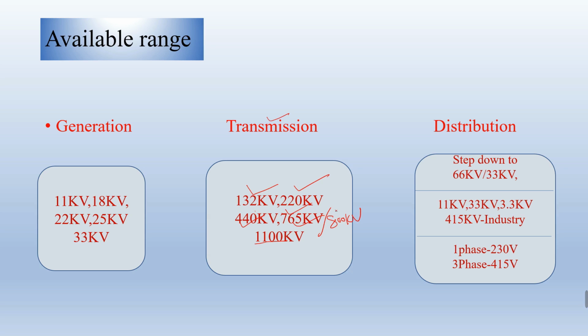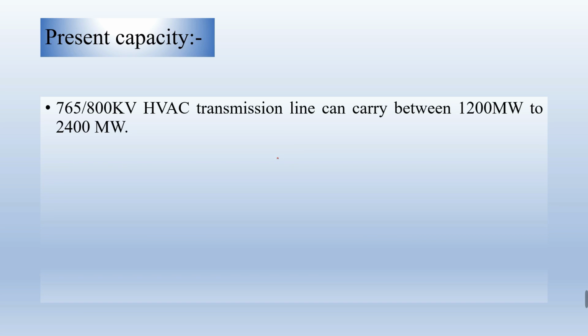Now let's see how much power this transmission line can carry. A 765 to 800 kV HVAC transmission line can carry between 1200 megawatt to 2400 megawatt of power. So if this 800 kV transmission line can carry this much power, then the 1200 kV line will definitely carry much more power than this, and that too with minimal losses.